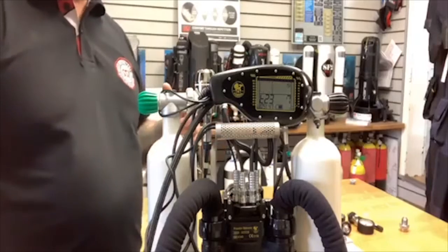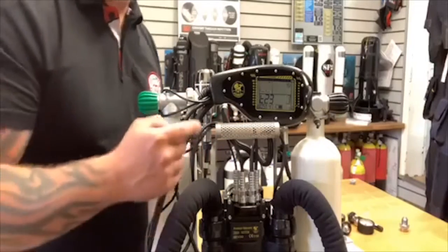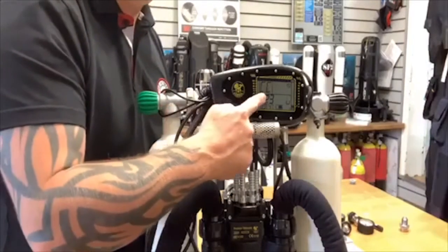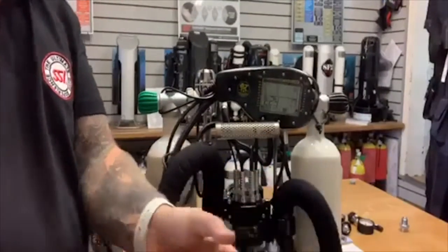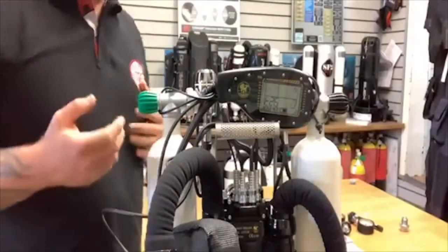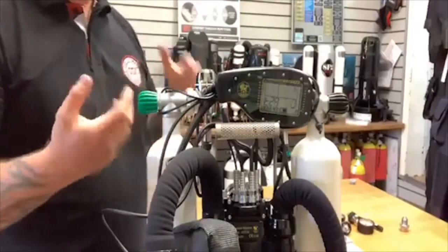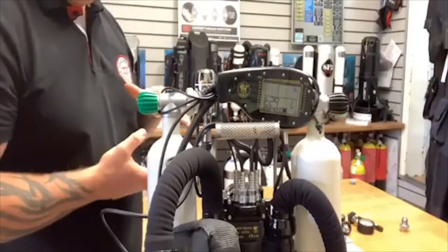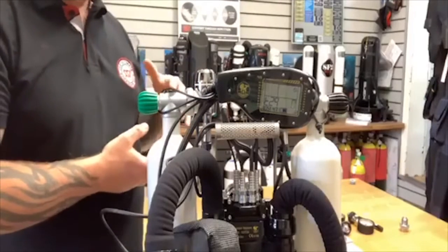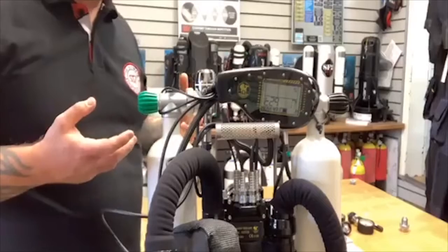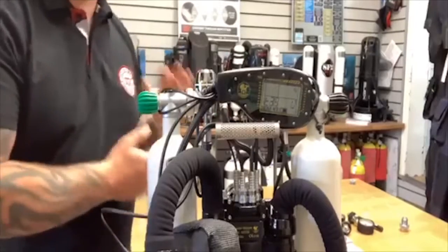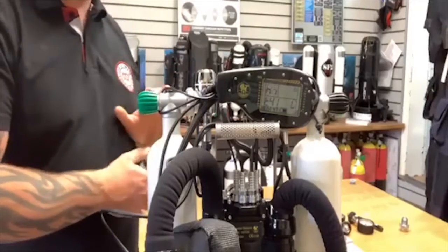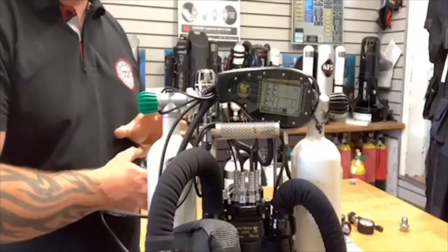And the machine's asking us to do something. What's it asking me to do? It's very simple. I can see it here on my display. It's saying CC. So I'm going to move this mouthpiece from this position to this position. What it's doing here is it's making sure that there's no volume inside the loop. A little bit later on, it's going to inject gas. If there was no scrubber inside the machine, the amount of gas that it would see when it injects would be greater. So it can detect a little bit whether there's a scrubber installed or not. It's not a perfect system, I'll be honest with you, but it is a way of checking.